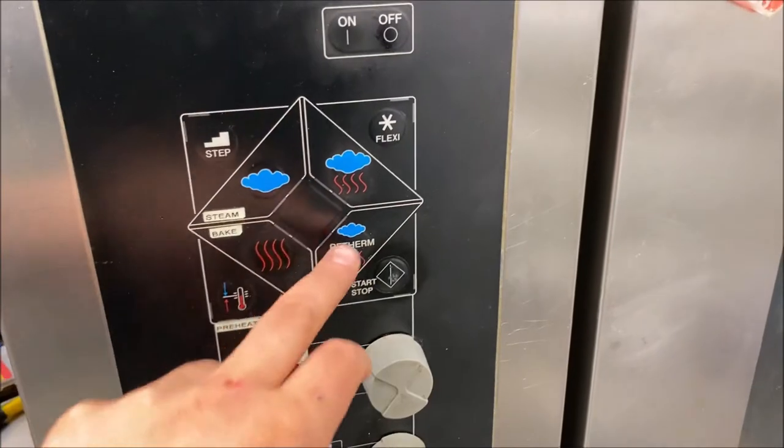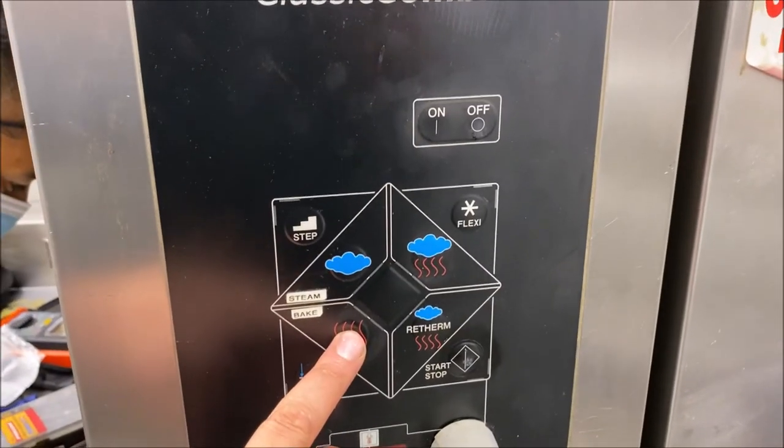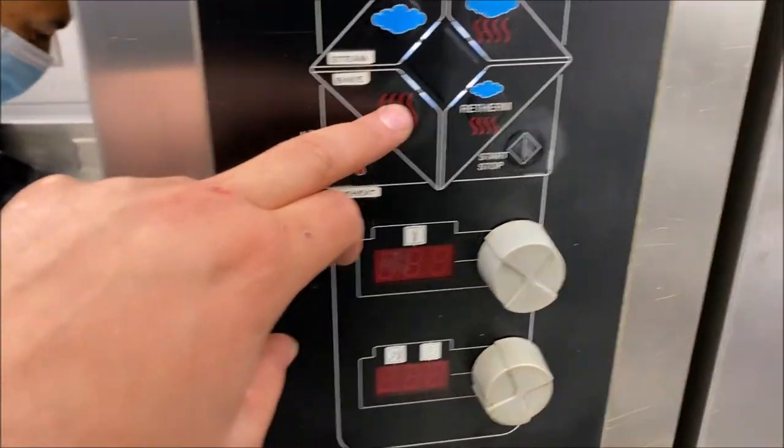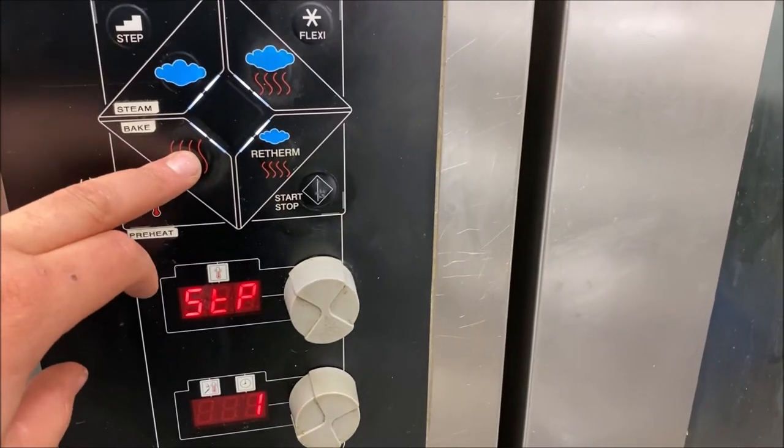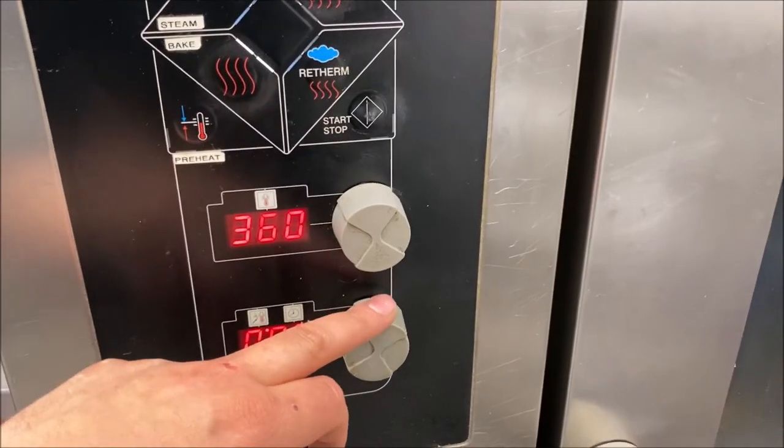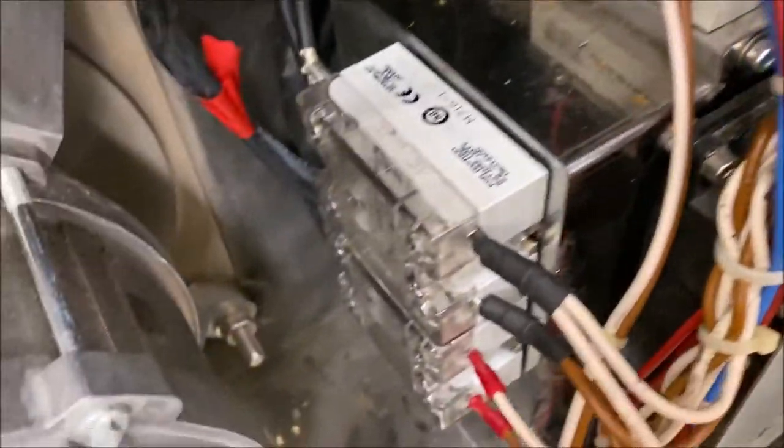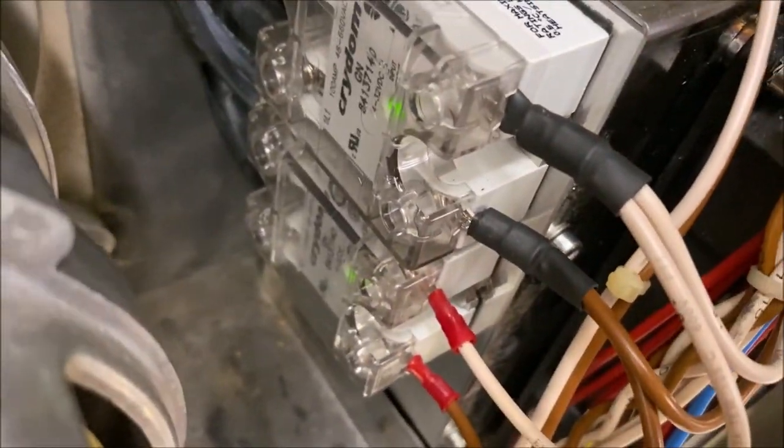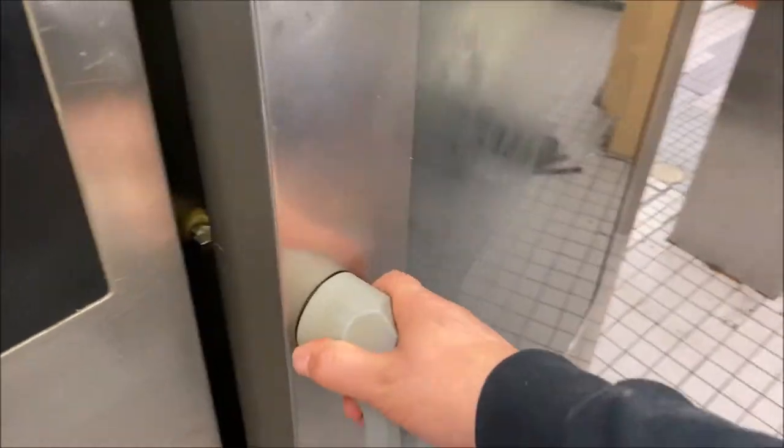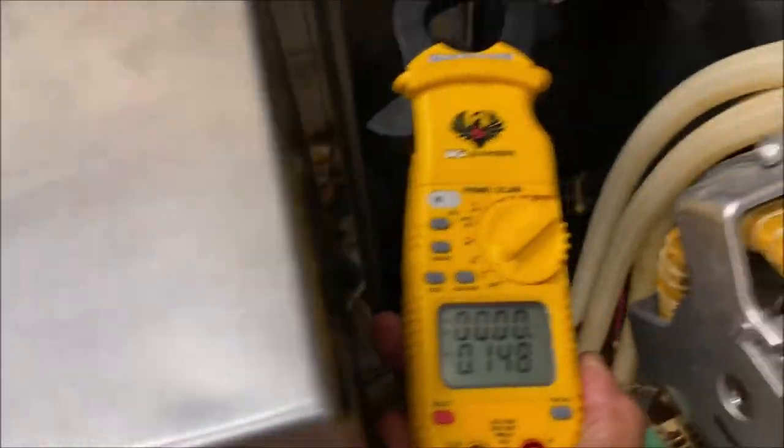Alright, so I'm back on site here. I've changed the element and that second relay, put everything in new. And we're just going to take our amp draws and make sure that none of the relays have failed closed, because I did have that other relay, that left relay I left in. So I just want to make sure that one didn't blow in the interim in the last two days. So we got 24 amps. Open up the door. Zero amps. Perfect.